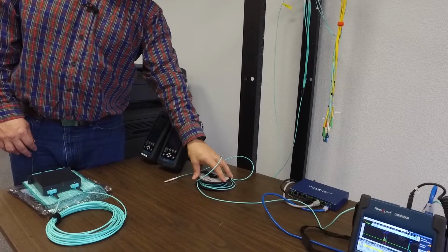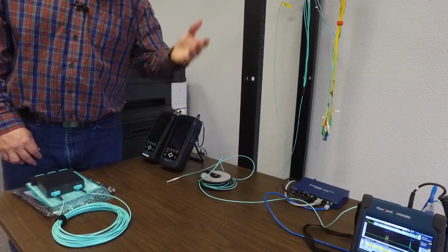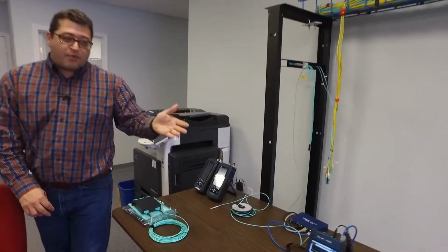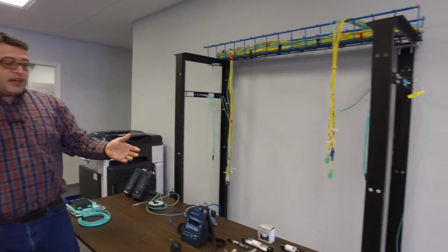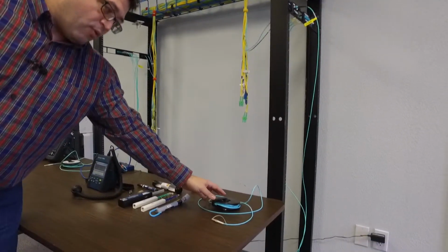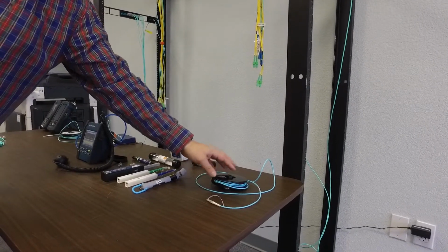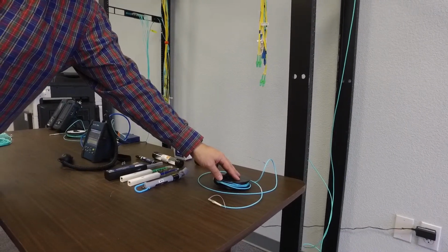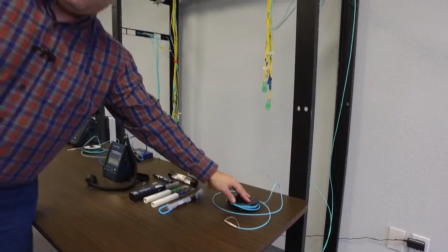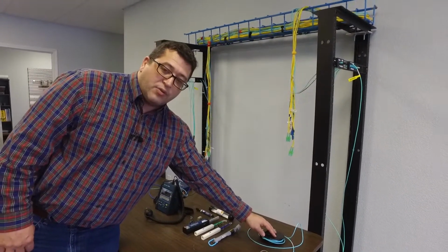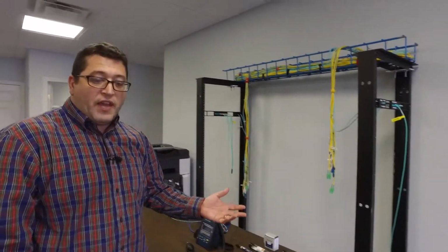When we're testing with the FiberXpert, we're going to be connecting a 500-foot launch cable to the front side of that link, and then on the back side of that link on the same fiber that's being tested, we're going to connect another 500-foot launch cable, but this, I guess we'll call it a tail cord on this side, so that we can have good vision of the last connector in the link. Okay, we want to be able to see the loss, reflectance, everything on that last link.